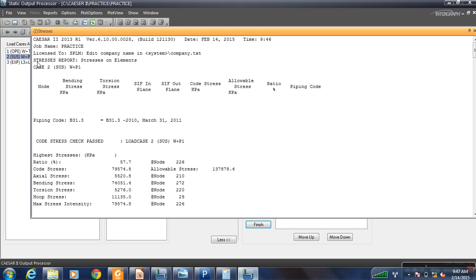There are four ratios. If our ratio exceeds more than 100, whatever we have designed fails — the pipe is over-utilized and supports are not enough. If the ratio is between 80 to 100 percent, the pipe will pass but the materials will be over-utilized. For example, if a plant has to work for 25 years, it may fail around 20 years. So this is also not desirable. If the ratio is less than 50, it means the strength of the pipe is under-utilized — you are putting way too many supports and you can reduce their number.